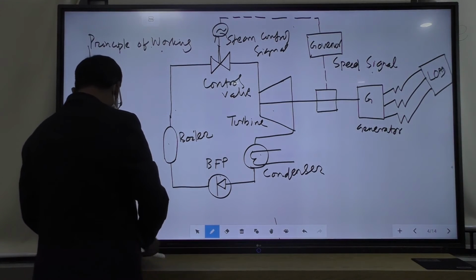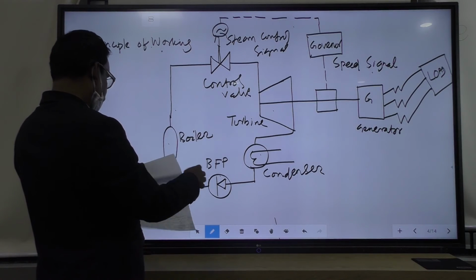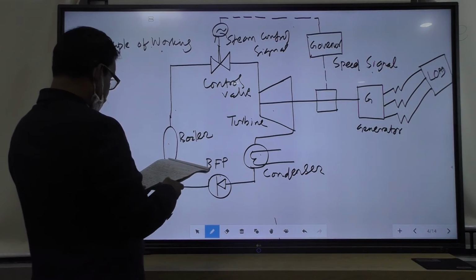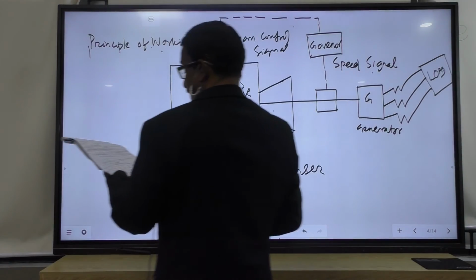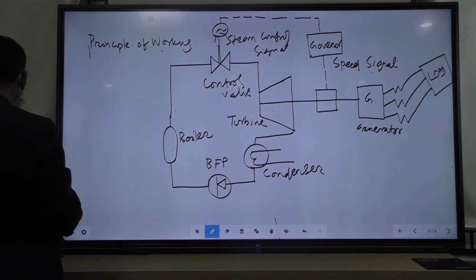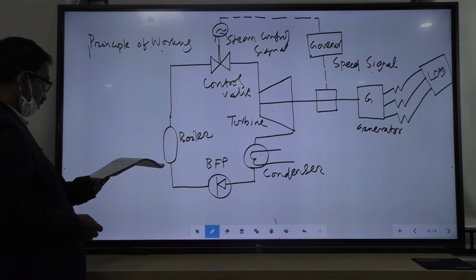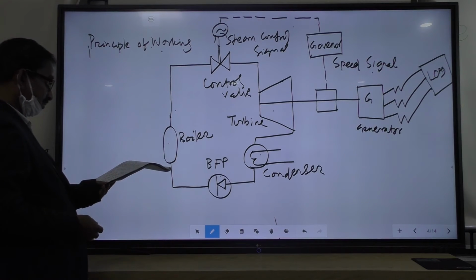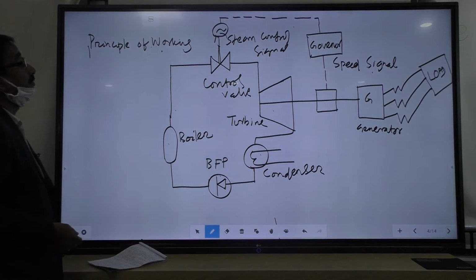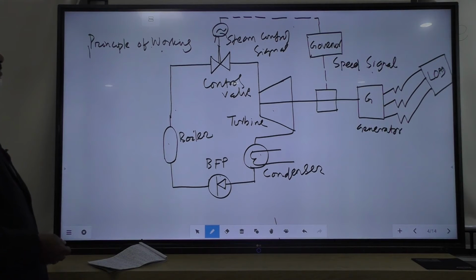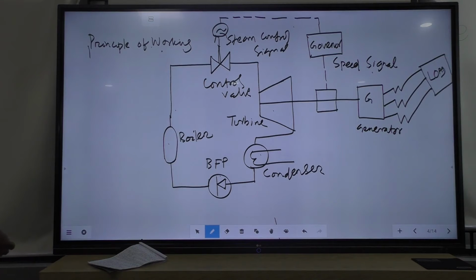So, the main task, I will explain. The main tasks of the governing system are to start the turbine from rest and run it to the rated speed and synchronize with the grid. So, the governor's main function is that it will start the turbine. That means the plant will be operated by the governor. The governor will start the turbine from rest condition and run it to the rated speed, that is 3000 rpm, and synchronize with the grid.